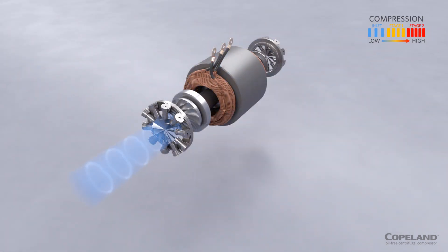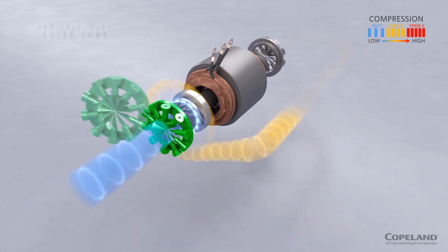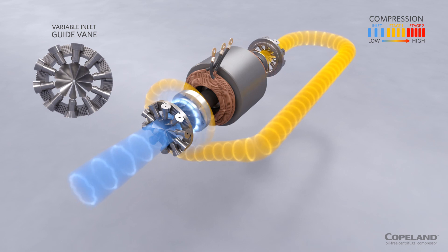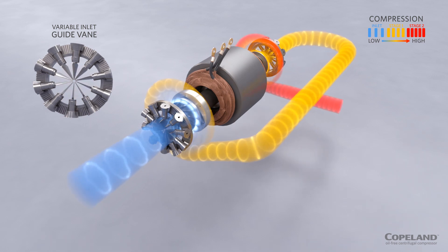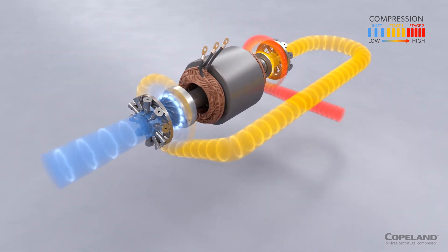As the first-stage impeller draws the refrigerant gas in, its flow is regulated by the variable inlet guide vane, which maximizes the compressor range in both surge and choke conditions.